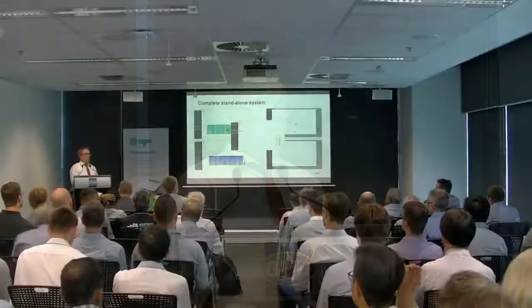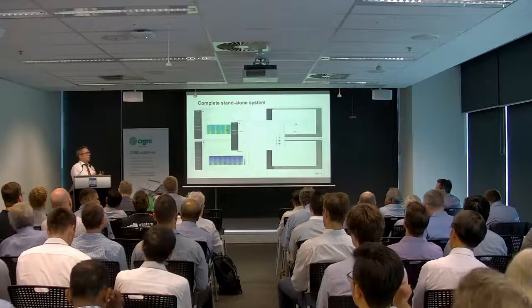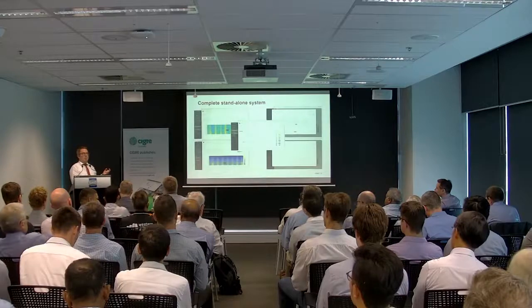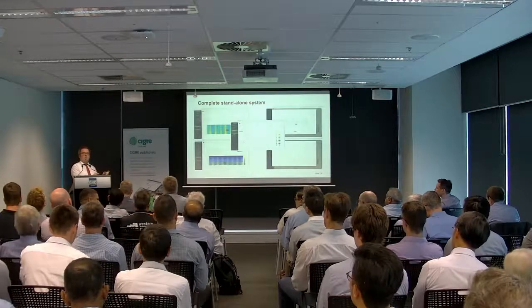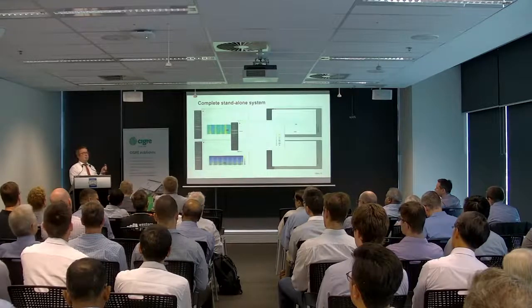Quickly wrapping up on the MV side, the experience from all three cases is that the voltage profile throughout the MV and down to the LV side was pretty much bang on. On the LV side of the distribution transformers, even in test networks where we had temporary loggers for comparison, we were usually within 1.5 volts, even at the most remote point. And mind you, the Bridgewater feeder, with something like 350 or 360 transformers, many of them single phase, had only 8 measurement points in total.